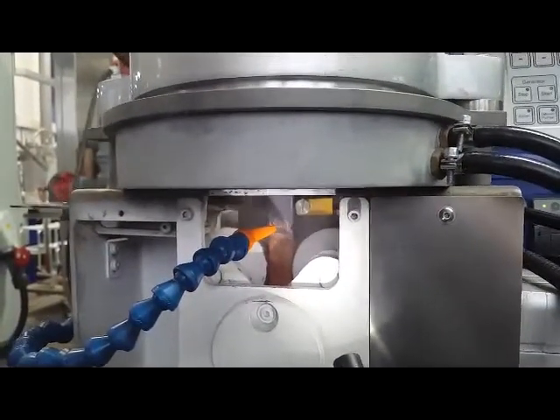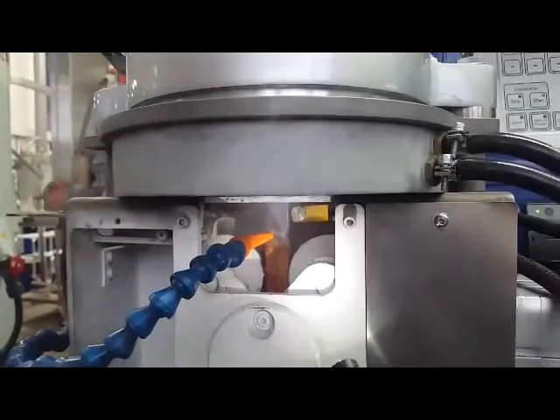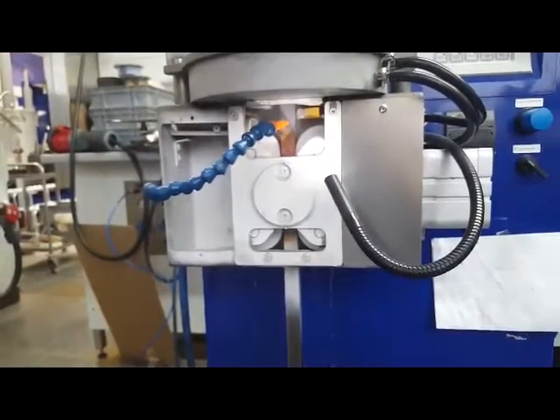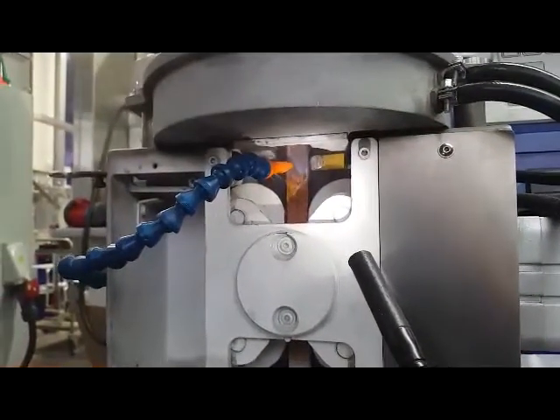If the die cooler is too weak, at a certain point the die cooler has a limitation. Since, as I mentioned, we do an indirect cooling. And then we can work with an additional direct cooling — in this case, it's like a water cooling.